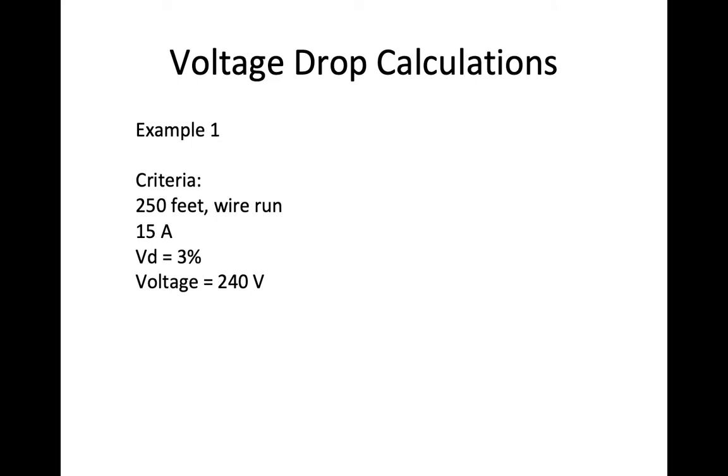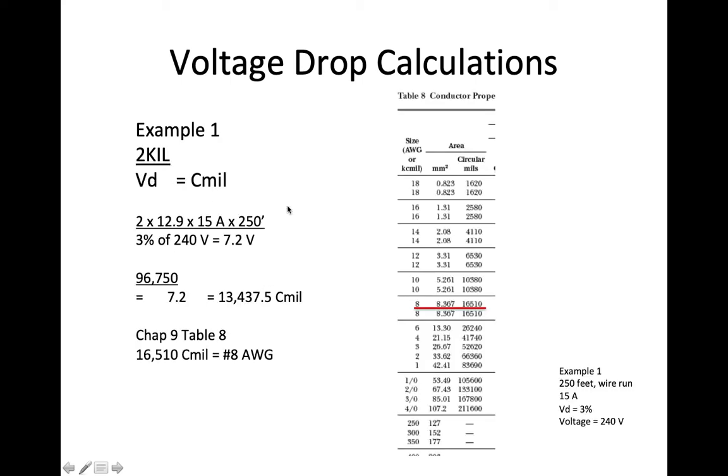Here's an example. I have 250 feet, wire run one direction, 15 amps, I'm going to limit voltage drop to 3% of 240 volts. Here's my formula. 2KIL Vd equals Cmil. I set it up. I always have 2.